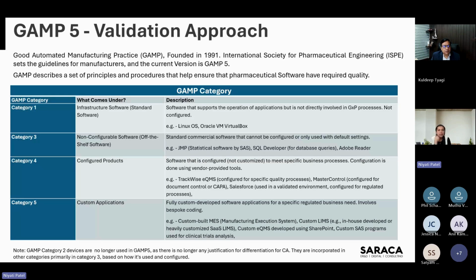GAMP also gives you a menu. It's a step-by-step menu of what to produce: your risk assessment, your URS, your supplier assessments, validation planning, functional specifications, design specifications, IQ, OQ, PQs, traceability matrix, and validation report. Those are some of the areas to touch upon when producing your deliverables using GAMP. And it's a practical step: you pick from the menu based on your system's category and its intended use.